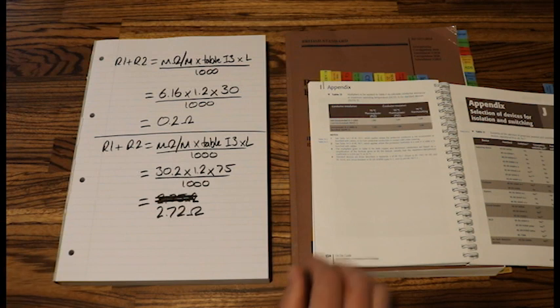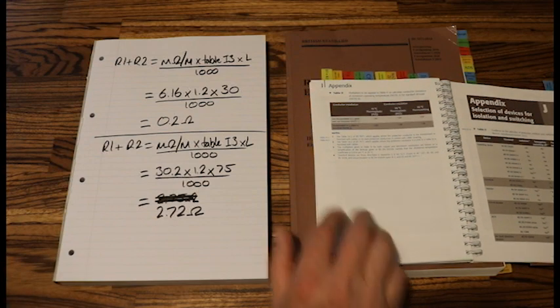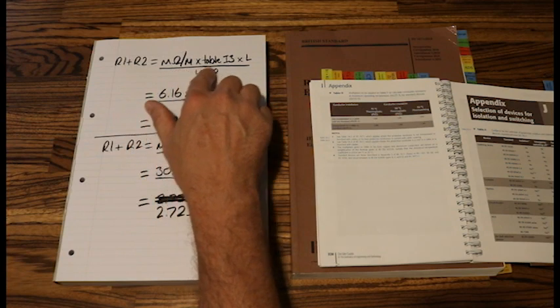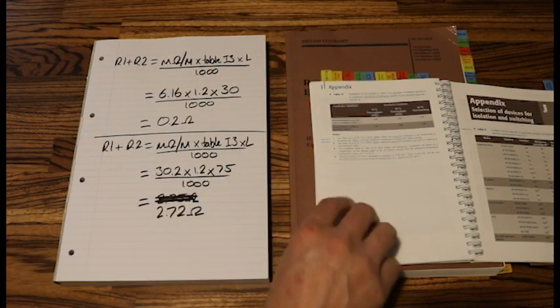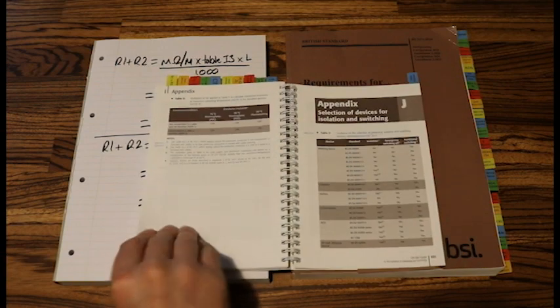What I would suggest to students is this formula here. R1 plus R2 equals milliohms per meter times table I3 times length divided by a thousand. I would write that at the bottom of your on-site guide's page 218.